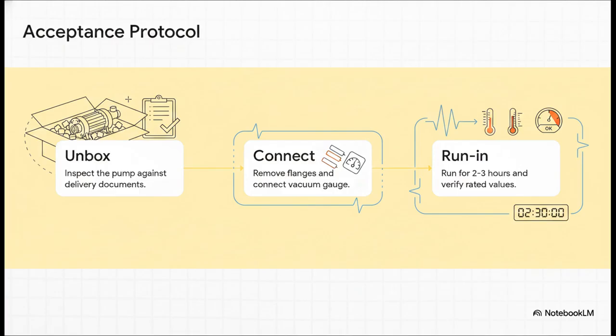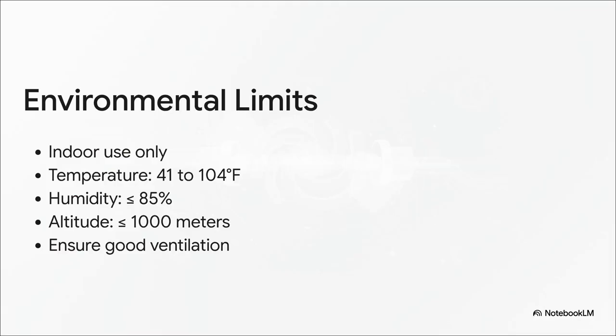You want to let the pump run for a solid 2 to 3 hours. This is your chance to verify that the ultimate pressure, the noise levels, and the operating temps match the manual, well before you ever connect it to your sensitive gear. Now, because we're dealing with high-precision mechanics, you have to rigorously control the physical environment.